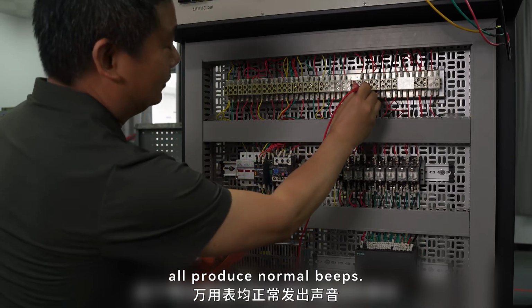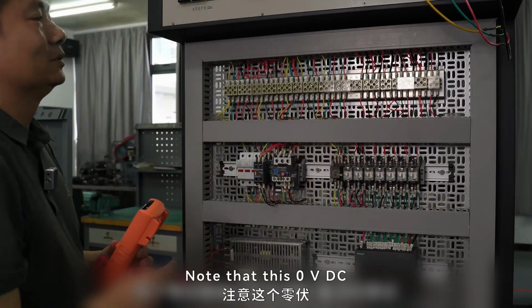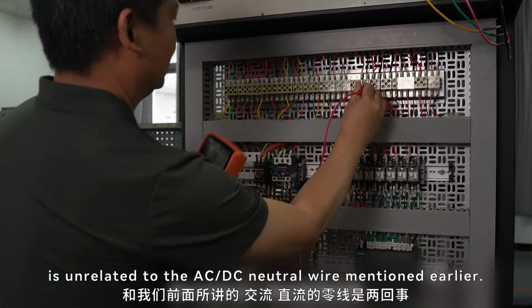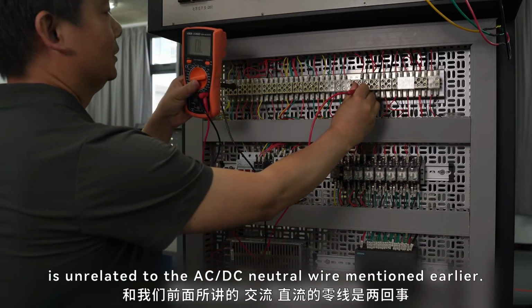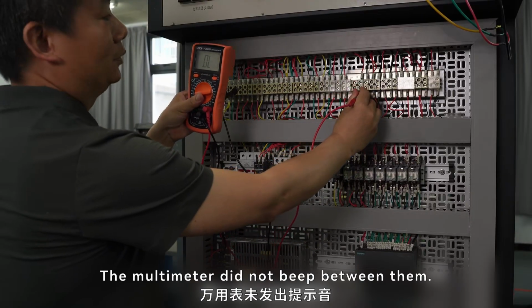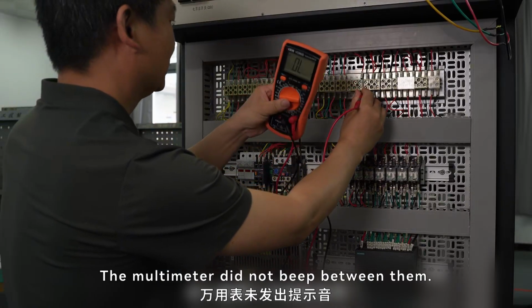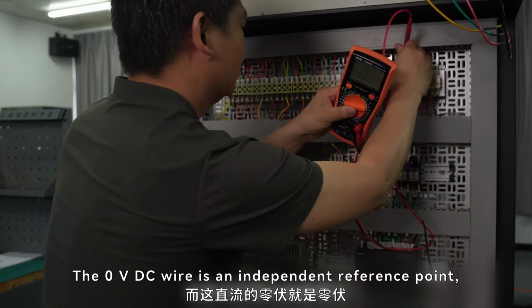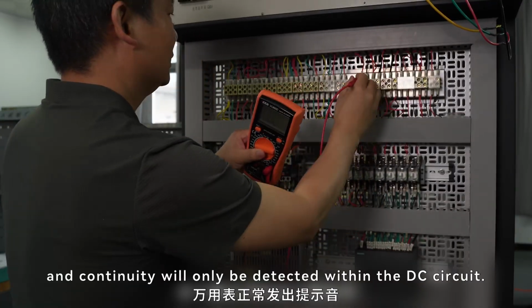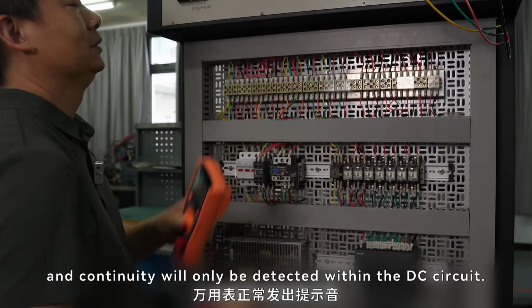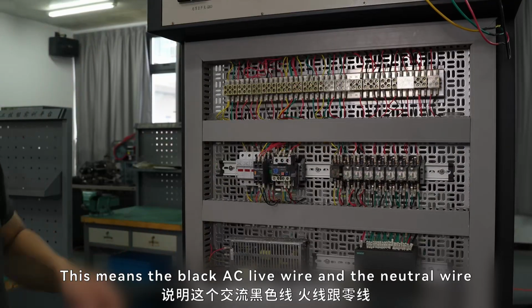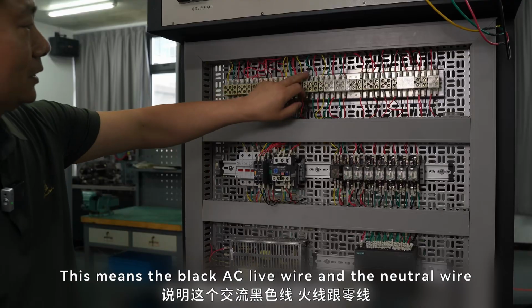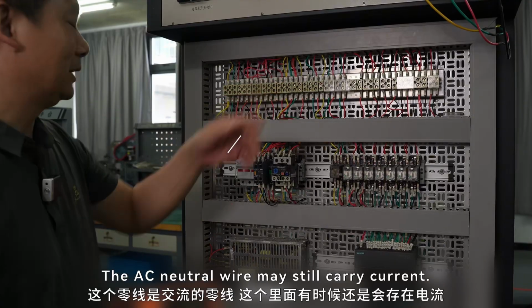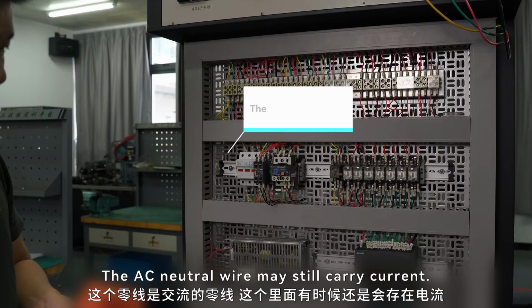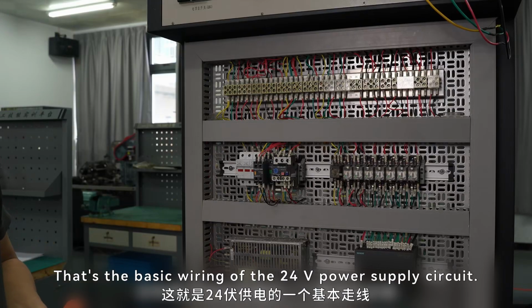All produce normal beeps. Note that this 0 volts DC is unrelated to the AC or DC neutral wire mentioned earlier. They are isolated. The multimeter did not beep between them. The 0 volts DC wire is an independent reference point, and continuity will only be detected within the DC circuit. This means the black AC live wire and the neutral wire are separate circuits. The AC neutral wire may still carry current. That's the basic wiring of the 24 volts power supply circuit.